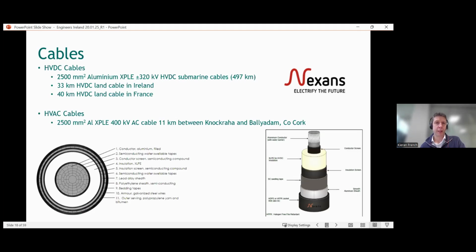It's a similar cable for the land portion in Ireland and France, 2500 square mil aluminium cable. It's not as mechanically protected as it would need to be for the marine cable, so a lot of the armoring wires etc. are not required for the land cable, but it's very similar in terms of its makeup. The image on the bottom left is actually the submarine cable. You can see we have profiled aluminium wires, not round wires, in 5 concentric layers around a core. We have our inner semiconducting layer, the insulation medium of the XLPE, the outer semiconducting layer, and the various lead sheaths, PE sheaths, bedding tapes, armoring wires, etc.